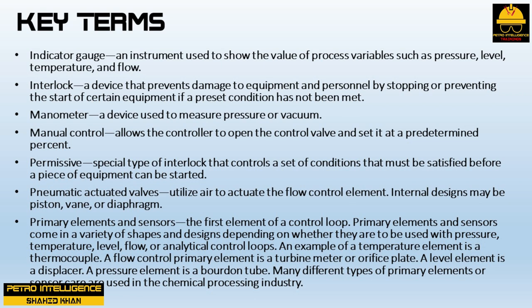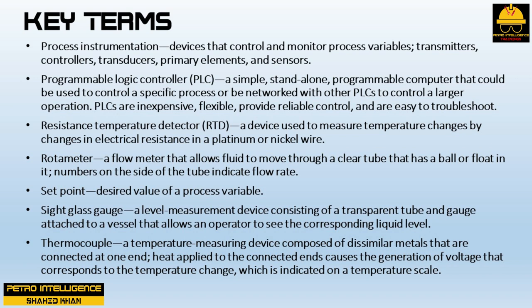Pneumatic actuated valves utilize air to actuate the flow control element; internal designs may be piston, vane, or diaphragm. Primary elements and sensors are the first element of a control loop and come in a variety of shapes and designs depending on whether they are used with pressure, temperature, level, flow, or analytical control loops. An example of a temperature element is a thermocouple; a flow control primary element is a turbine meter or orifice plate; a level element is a displacer; a pressure element is a Bourdon tube.